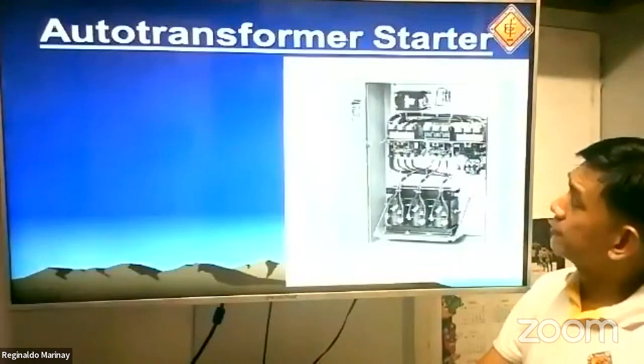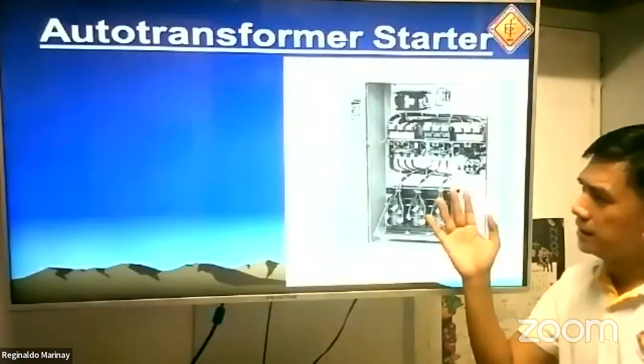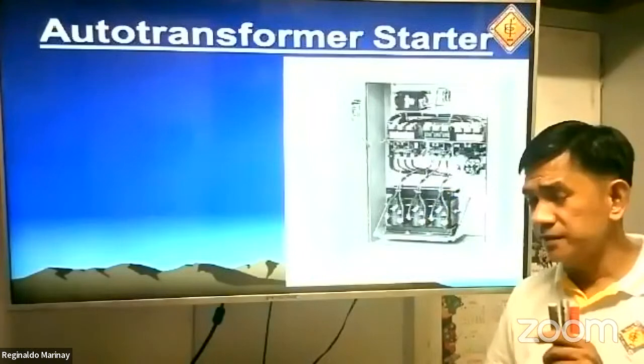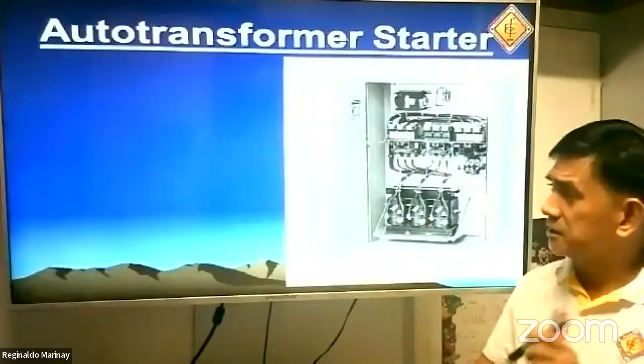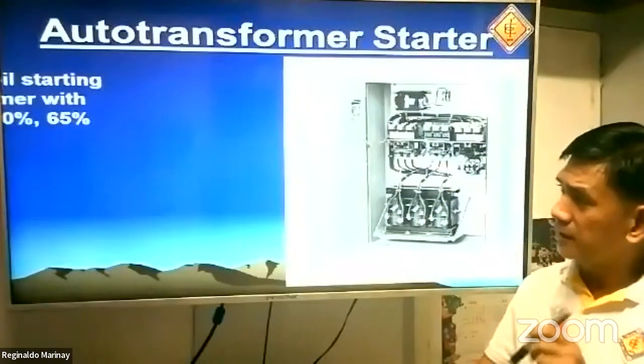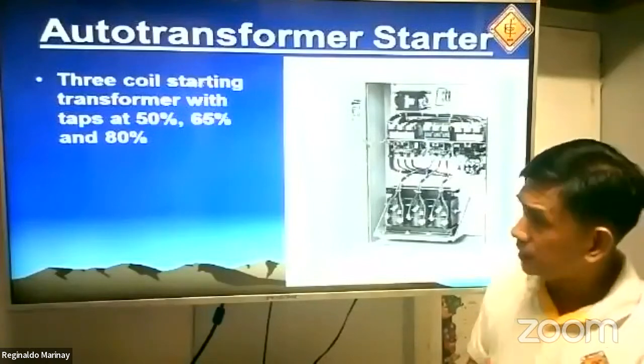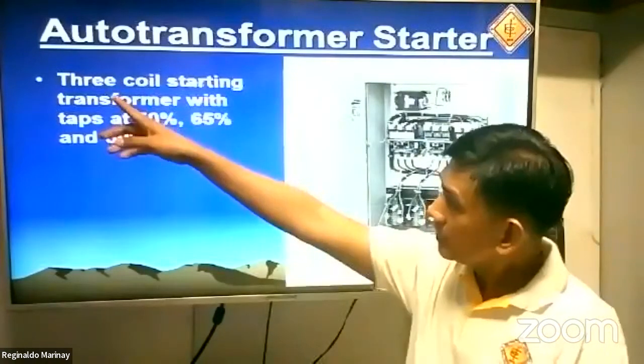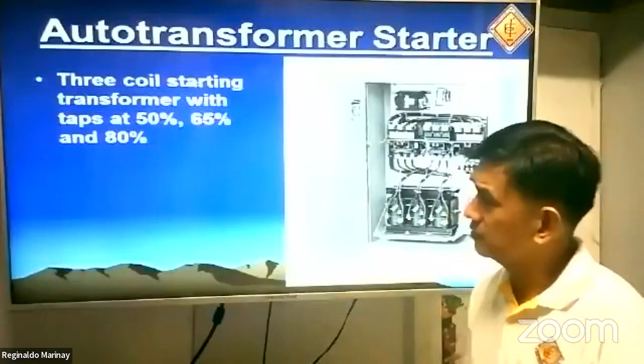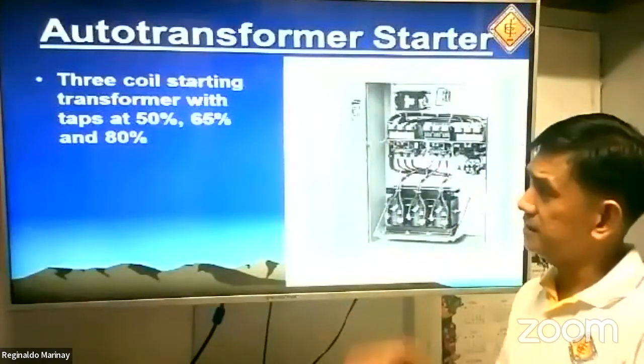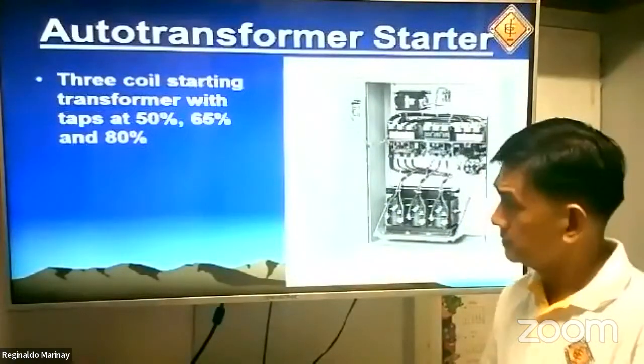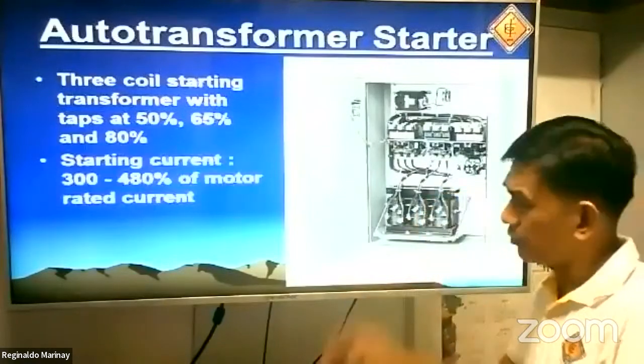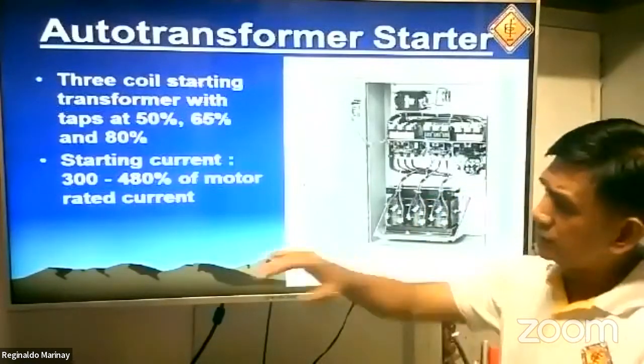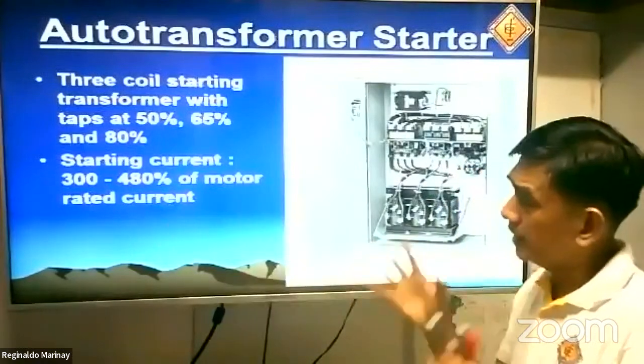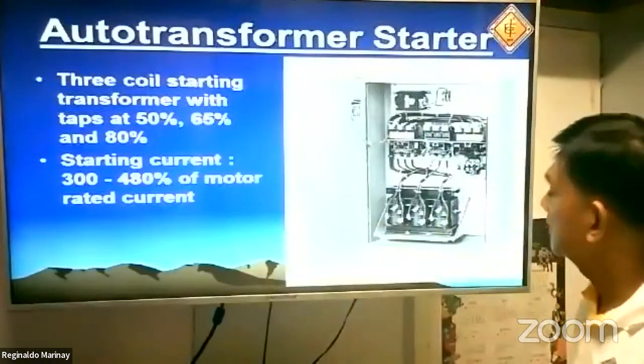Let's go with the auto transformer starter. Take a look here. The principle of the auto transformer is quite similar to the resistance starter. So, a 3-coil starting transformer with taps at 50%, 65%, and 80%. So we're going to use the transformer tap setting. We can reduce the starting current to 300 to 480 percent of the motor rated current.